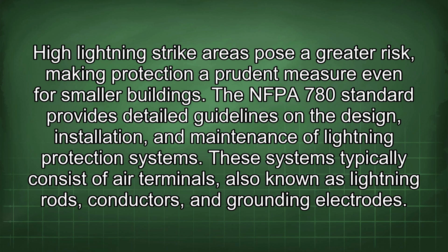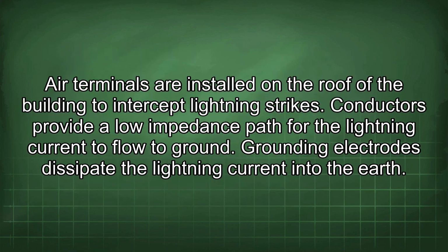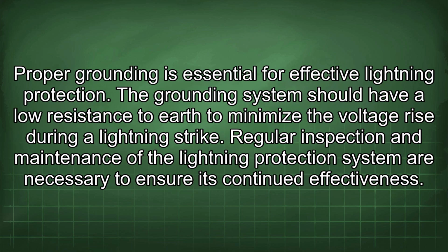These systems typically consist of air terminals, also known as lightning rods, conductors, and grounding electrodes. Air terminals are installed on the roof of the building to intercept lightning strikes. Conductors provide a low impedance path for the lightning current to flow to ground. Grounding electrodes dissipate the lightning current into the earth. Proper grounding is essential for effective lightning protection. The grounding system should have a low resistance to earth to minimize the voltage rise during a lightning strike.